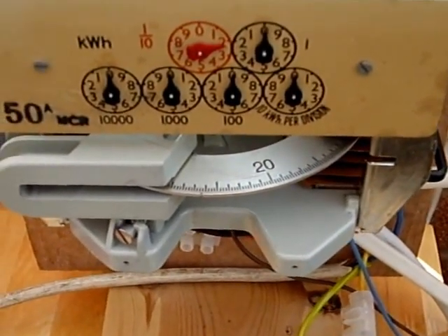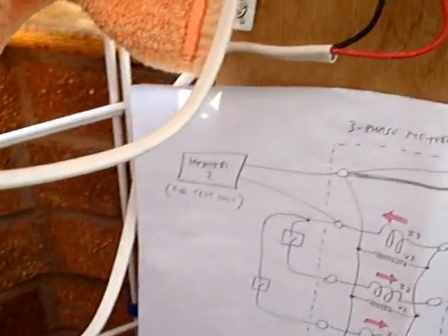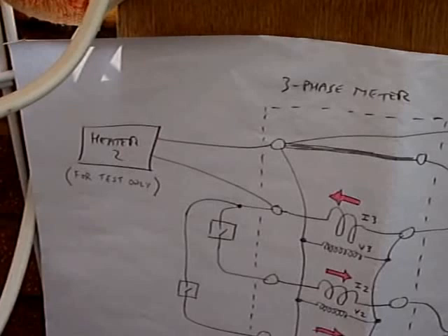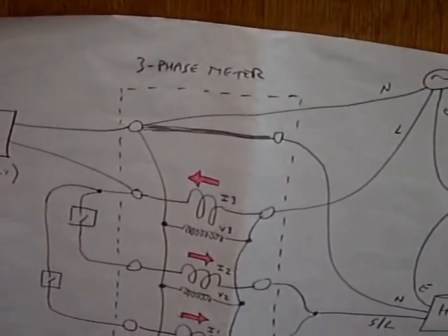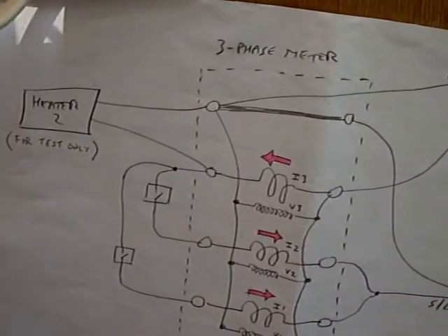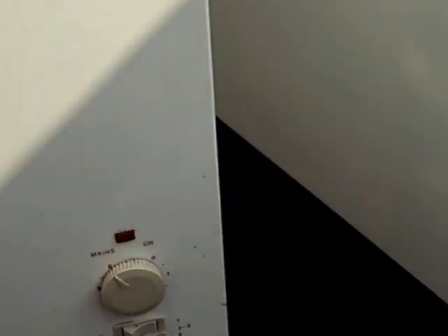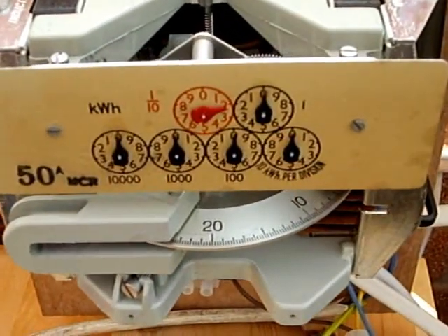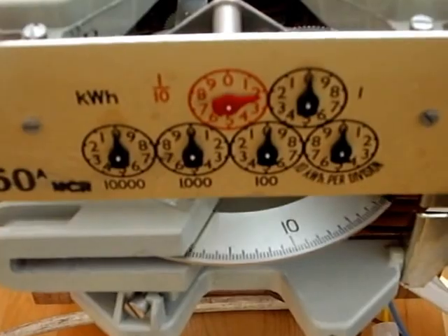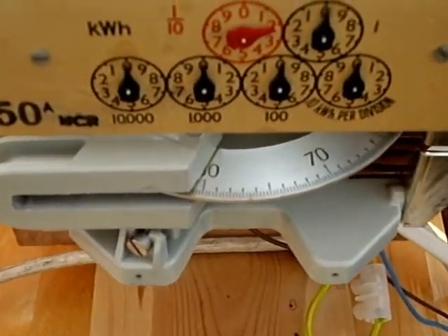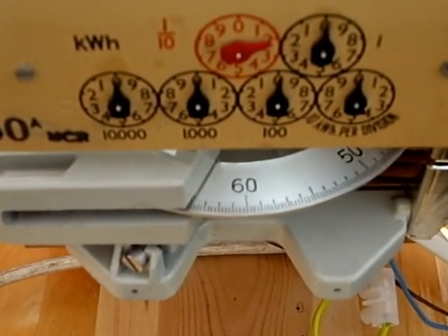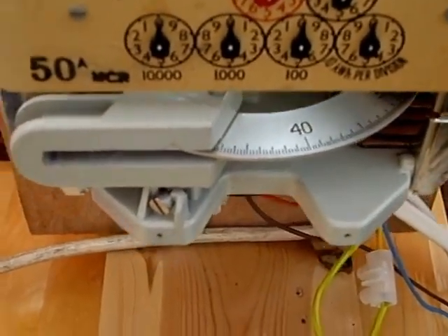Just to demonstrate that what really is happening is indeed the case, I've got this second heater here, and if I were to switch that one on, then as you can see, current only gets pulled for that heater through the upper of the coils. It gets back via an alternative route, it doesn't go via the lower coils. So if I put this heater on to, say, 1 kilowatt, now the meter is moving substantially. If I were to put on 3 kilowatts, we're now seeing a substantial movement. So that's what 3 kilowatts looks like, just pulling this along through one coil.